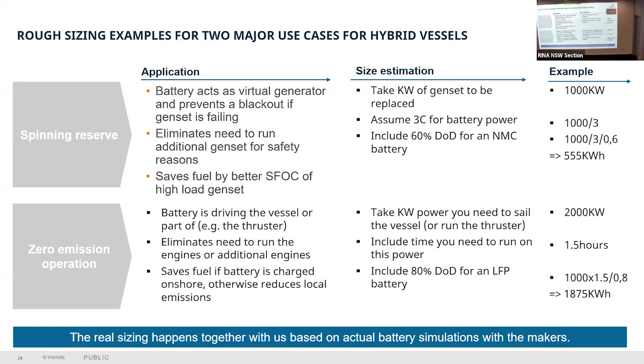Another is zero emission operations. The battery is driving the vessel, or part of it, let's say a thruster as well. We take the kilowatt power needed to sail the vessel, let's say 2000 kilowatts. Then we include the time. Let's say we want to use that power for 1.5 hours. We include 80% depth of discharge for an LFP battery. We multiply 1000 into 1.5 and divide by 0.8, which is 1875 kilowatt hours.